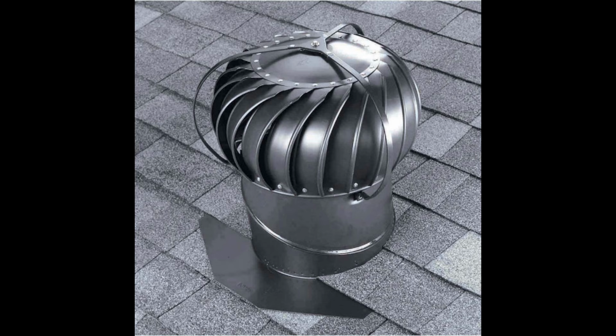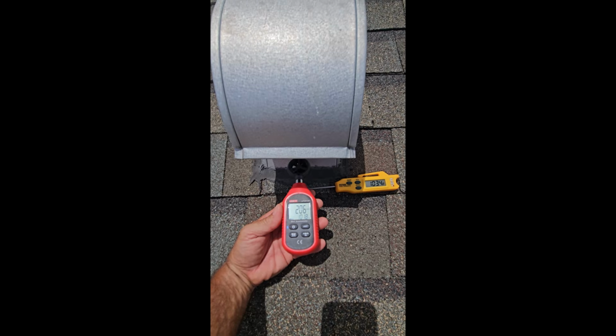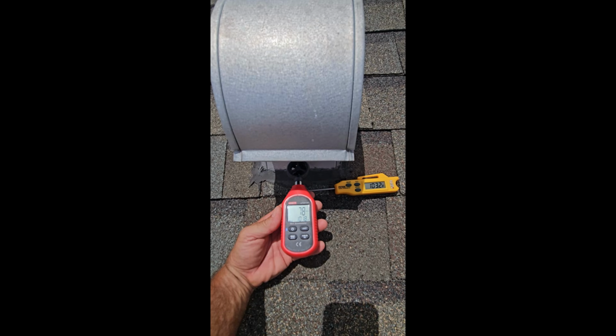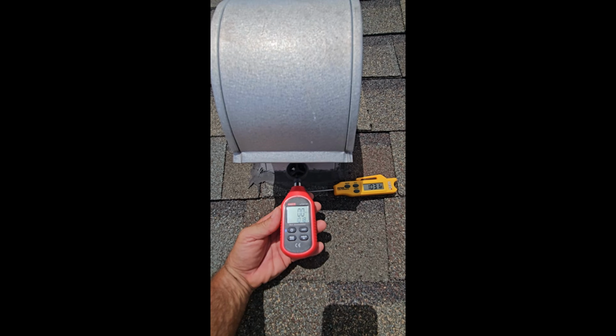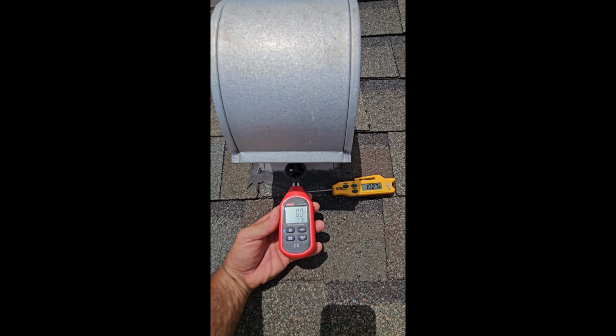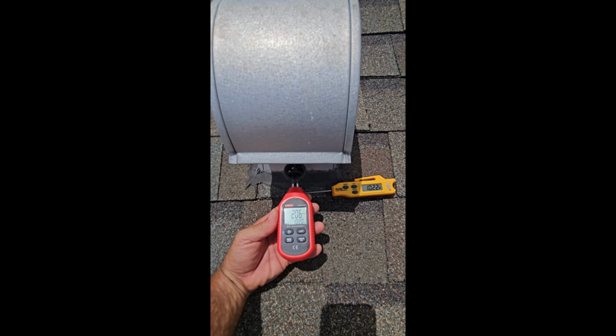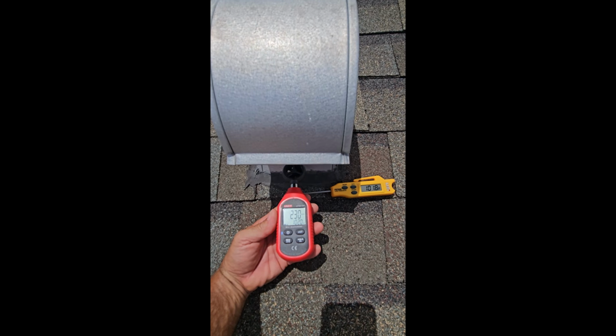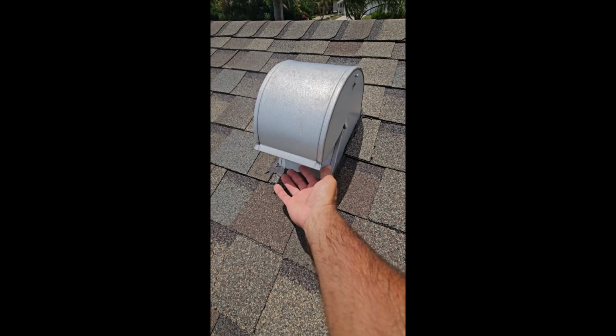Whirlybirds or roof wind turbines aren't as nice looking, but they do have more airflow. Today is moderate wind, so you can see right here with a flow meter, the feet per minute out of this vent is between 0 when there's no breeze and up to 250 feet per minute when there's moderate wind. The air temperature exiting the attic is off to the right.